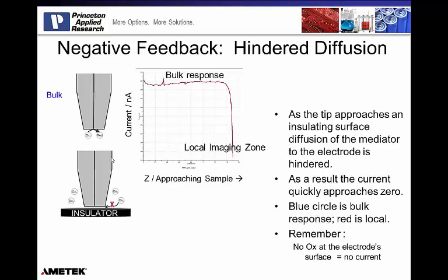If I had a very thin piece of glass, or the RG ratio is a very small number, that would still allow the ox target ion to reach the platinum wire. Take the even more extreme example of no glass at all. We would still have access of the ox to the platinum wire, and our current would still be at the localized level. So we seal that in glass. That allows us to restrict access of ox to the platinum wire over an insulating surface. So that is what is happening from the probe standpoint in the system.